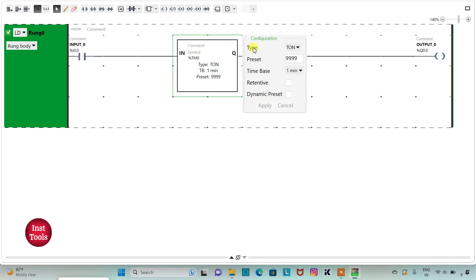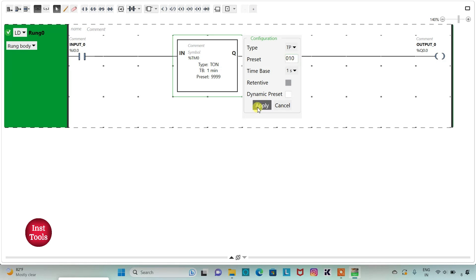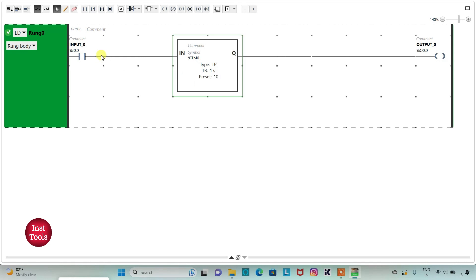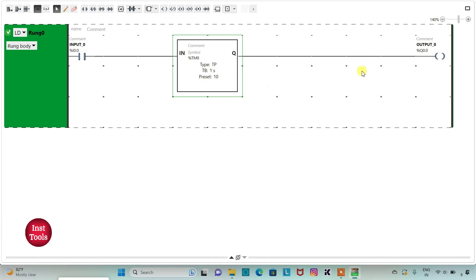I will select it as TP Time Pulse, then set the time base as 1 second and the preset value as 10, and then click on Apply. So when Input 0 is on, Output 0 will be on for 10 seconds, and after that it will automatically be turned off even if Input 0 is still on.